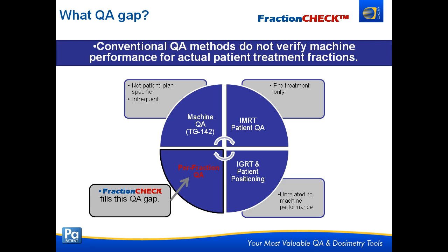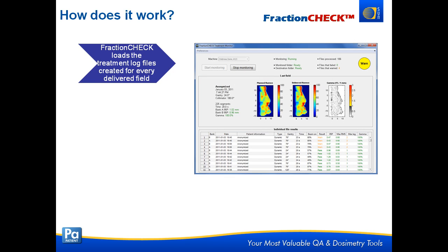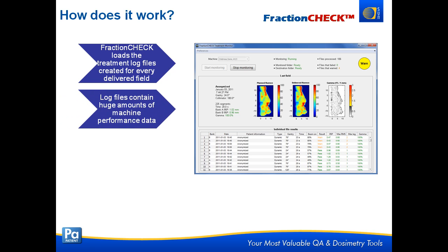FractionCheck fills this gap and gives you all four pieces of the pie. The really nice thing about it is that it uses machine logs and everything happens automatically. As a physicist, I know we don't have all the time in the world in our clinic, and we'd like to do as much QA in as little time as possible — that's really how we design our products. FractionCheck loads treatment log files that are automatically created for every delivered field. Varian systems create Dynalog and Trajectory logs automatically. FractionCheck launched with Varian support, but in the next couple of months we're also going to support Elekta, with our own log file writing tool so it works exactly the same way.